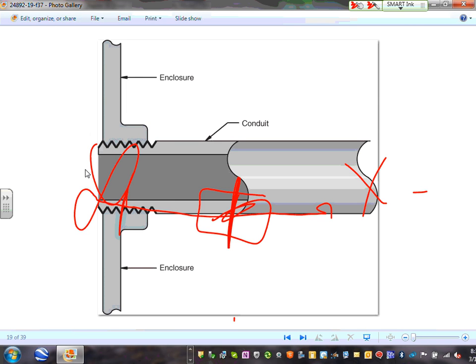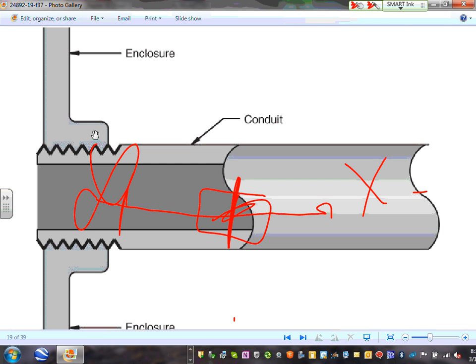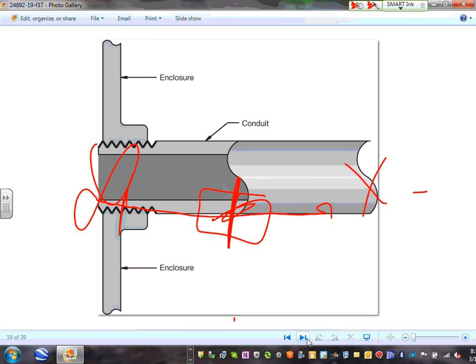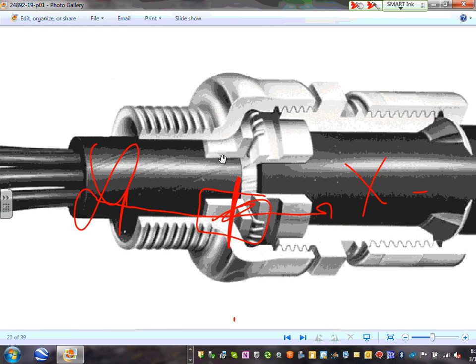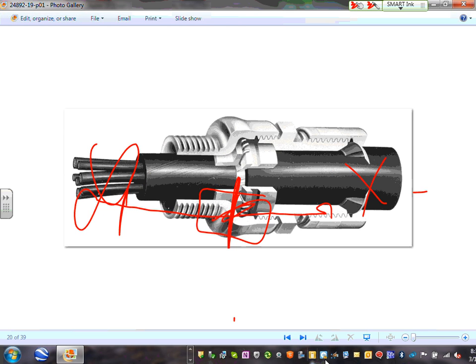Threaded, look at that, guys. You have to have a threaded system. You cannot use EMT, for example, in class 1, div 1, and div 2 location. It's all threaded. Cables, guys, are threaded and sealed that they use.